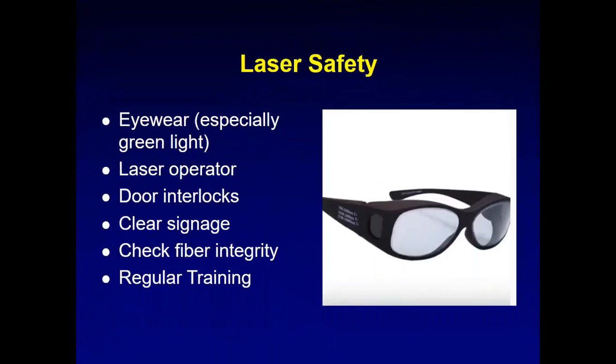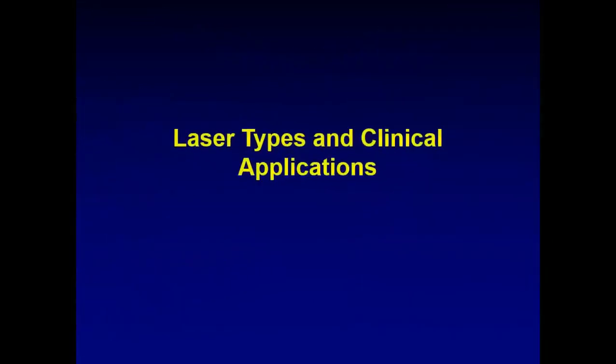You should be wearing goggles, especially for green light. It is very dangerous for the eyes. Laser operators should know, and everyone present in the room should know, what the precautions are. Doors should be locked, fiber integrity should be checked, and regular training should be done for lasers, to check whether it is working properly or not.